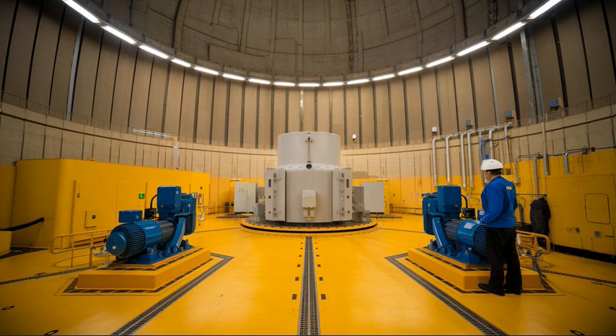Motor efficiency and reliability. Select motors designed for high efficiency and reliability to minimize energy consumption and reduce the risk of failure, minimum IE3 efficiency. The motors shall also comply with industry standards like NEMA, IEC, and AFCEN's RCCM and RCCE codes. Seismic qualification. In nuclear environments, the motors must withstand seismic events. Ensure that motors are seismically qualified according to the required plant standards, such as IEEE 344 or RCCE.